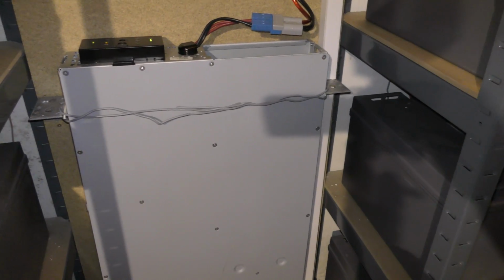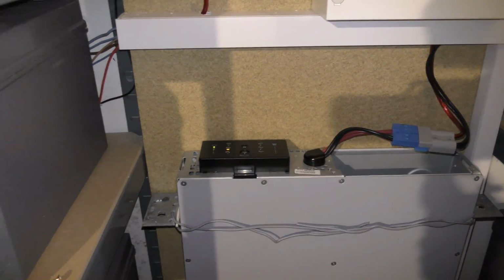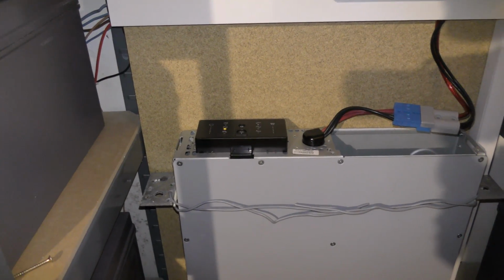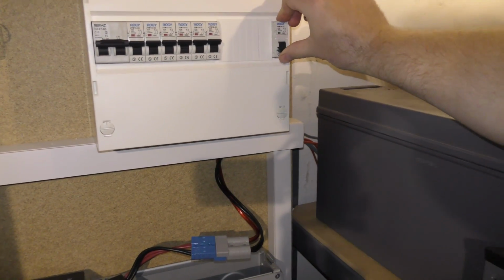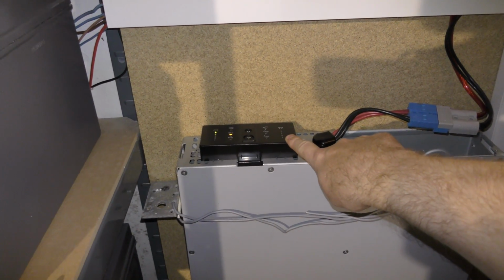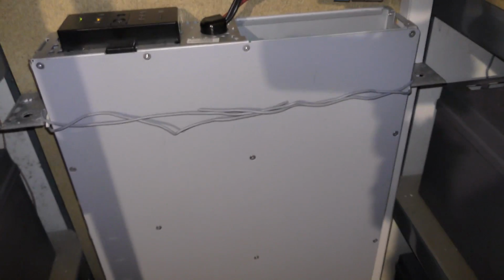Let's turn that off again. Okay, I turned off the vacuum cleaner. It's still a whiny little thing about the battery bank and probably the battery voltage, but as soon as I turn on the power out to the data center, it's gonna see that in just a second when the automatic transfer switch out there kicks in. You can hear this vibrating. It does not like that much.